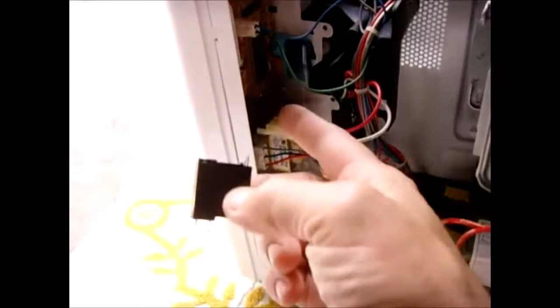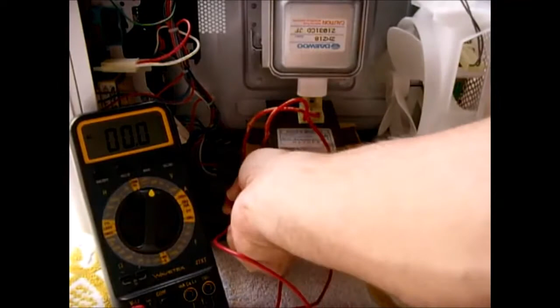The next step is to disconnect the power and discharge the capacitor once again. Once the capacitor has been discharged, you're going to take your digital multimeter on the high voltage AC setting, connect up one of the alligator clips to one of the probes, reach in with the other end, and clamp it onto the blade terminal of the primary side, which is the wires coming from the board. You don't want to touch these red wires. Stay away from these, anything going to the capacitor - those are all high voltage.